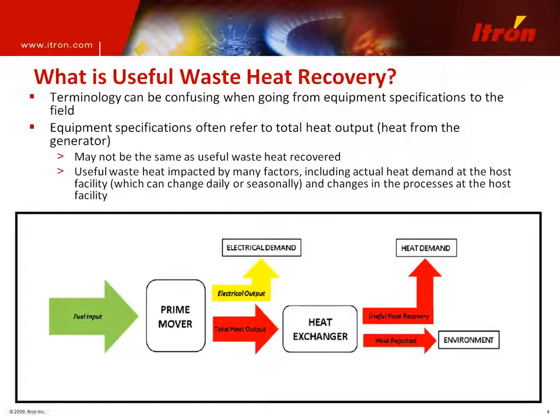Useful waste heat is really impacted by a number of factors. One of the things that is critical to understand is that it's going to be impacted significantly by actual heat demand at the host site. And that can change daily. It can change based on what's happening with the demand within the existing processes, or there can be changes in processes at the host site. So it's important to understand that impact on what you define as useful waste heat recovery. Next slide.